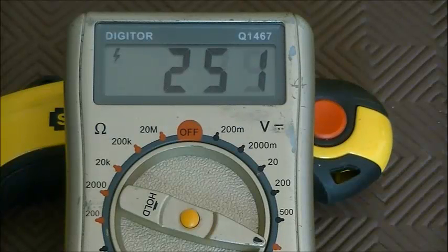Alright, we've just done a couple of experiments with an ordinary duty lead, and we've proven that the voltage drop is proportional to the length of the lead given the same current. You'll recall that we were losing roughly round about 1 volt per metre of lead with my jug plugged in, which is probably around 8 to 10 amps.